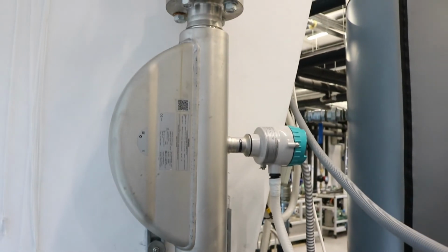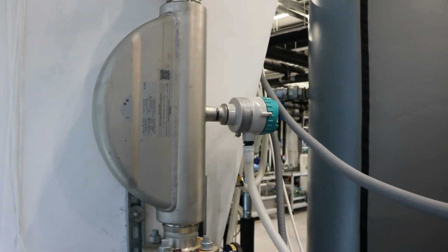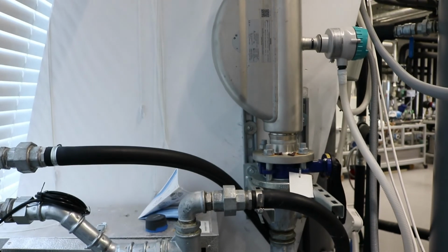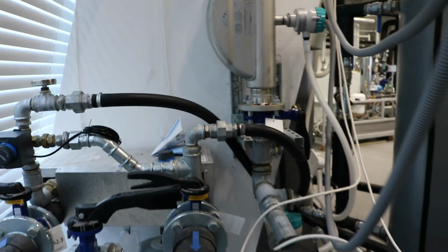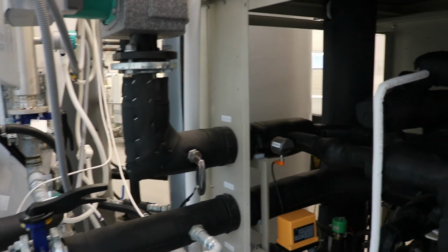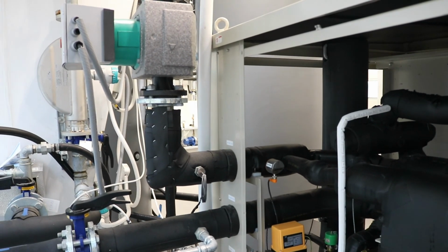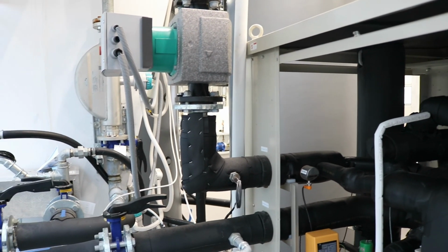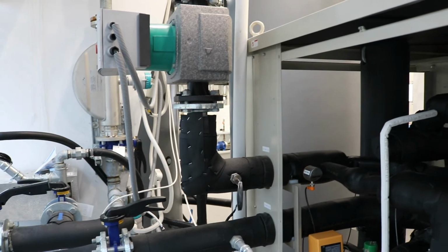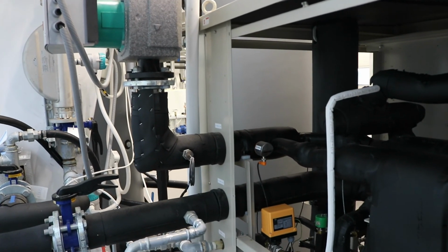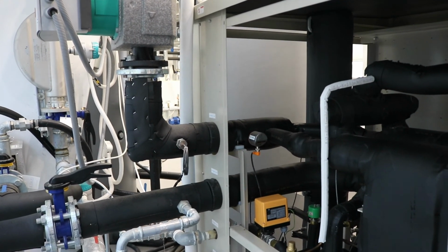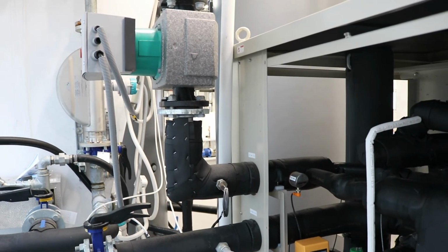We use these measurements to calculate the heat delivered and heat taken, as well as the measurements of electricity used to power the compressor. With these measurements and calculations, we know characteristics of this heat pump, and we can calculate the COP or EER.